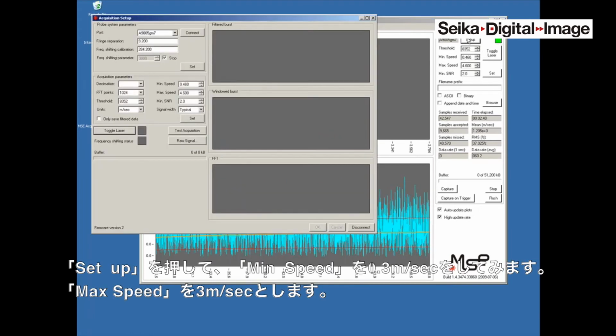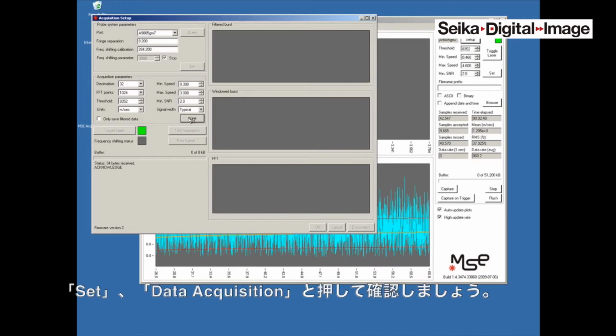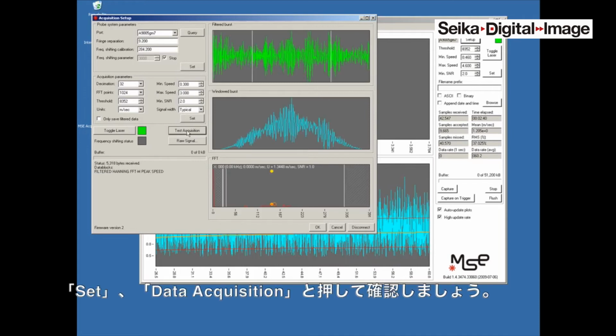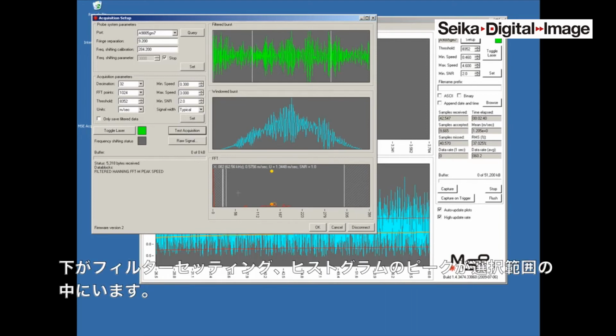So I go to setup. Actually, we could have done it here in the minimum speed, but let's say minimum speed of 0.3 meters per second to 3 meters per second, and we take a test acquisition just to make sure that our filter settings and our histogram are fine, the peak histogram is within the accepted area.